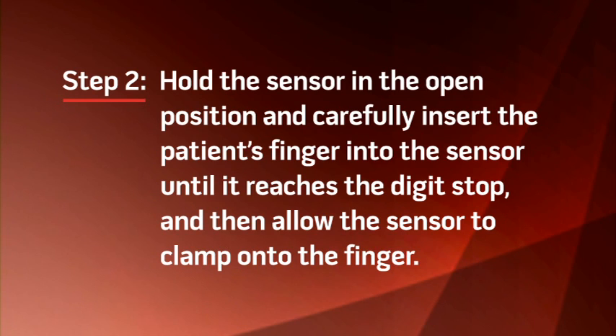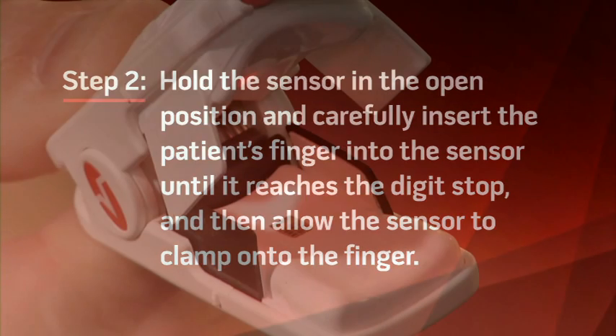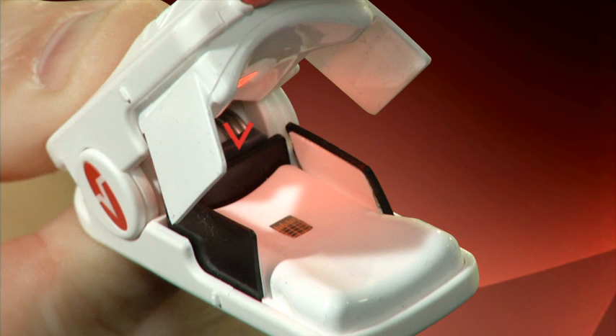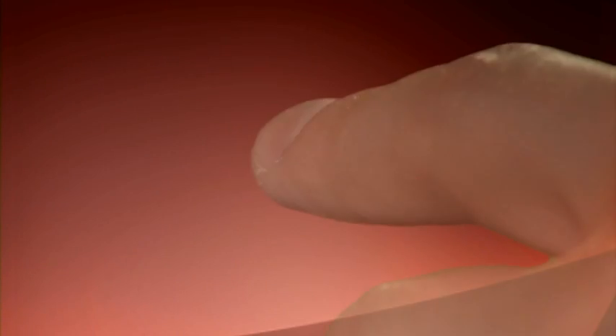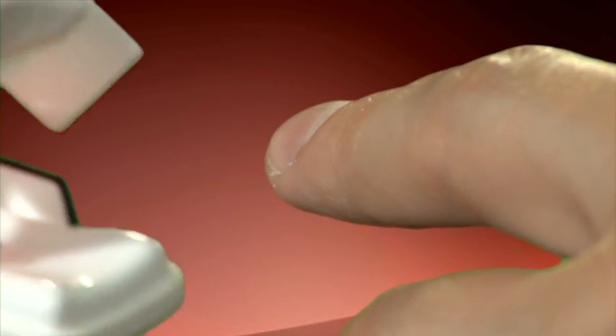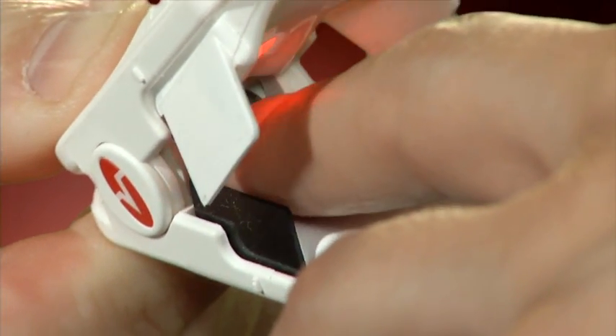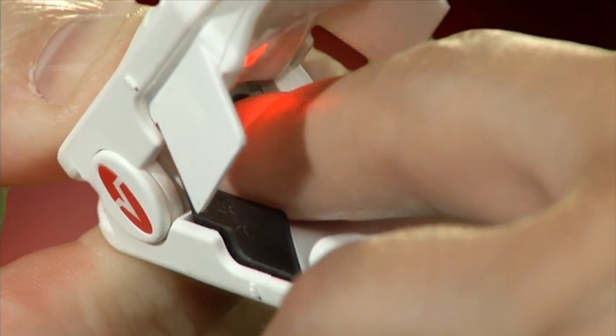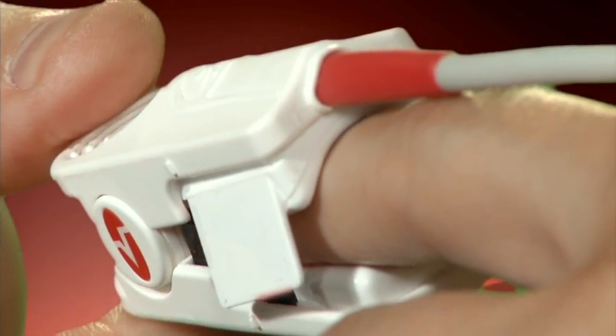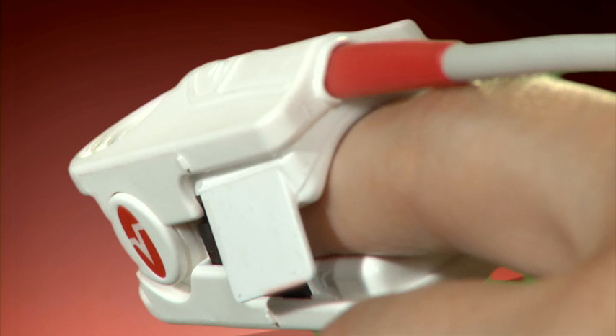Step 2. Hold the sensor in the open position and carefully insert the patient's finger into the sensor until it reaches the digit stop, and then allow the sensor to clamp onto the finger. The digit stop is a small black elevated block located on the bottom of the sensor near the hinge. It is very important that the finger is inserted all the way until it touches the digit stop. Not inserting the finger far enough or inserting the finger too far may result in inaccurate readings. The patient's fingernail may extend over the stop tab.